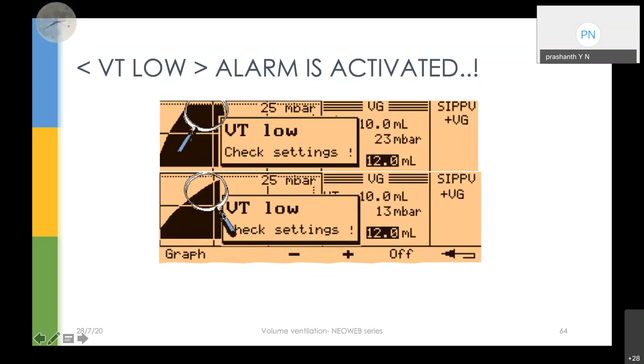And here, the pressure graph is going up and you see that there is no plateau at all. So probably if I increase the flows, I will get a plateau, and the tidal volume will get normalized. This is an example of setting low flows when you're using volume guarantee, because we know flow rate also contributes to the tidal volumes.